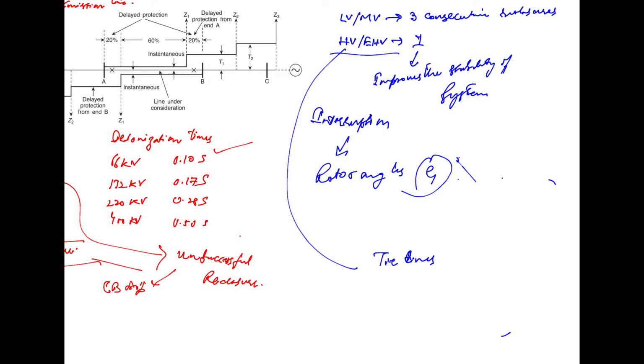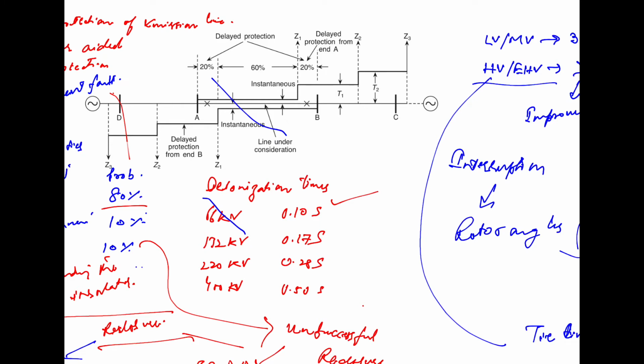As we have discussed, the 3-step distance protection for the entire line length does not meet the requirement of instantaneous and simultaneous tripping from both the ends. In the previous modules we have seen that only 60% of the length of the line, in the middle of the line, gets high speed protection from both ends. For about 20% of the length of the line near each end, that is a total of 40% of the line length, the protection is instantaneous from the local end but is delayed from the remote end.